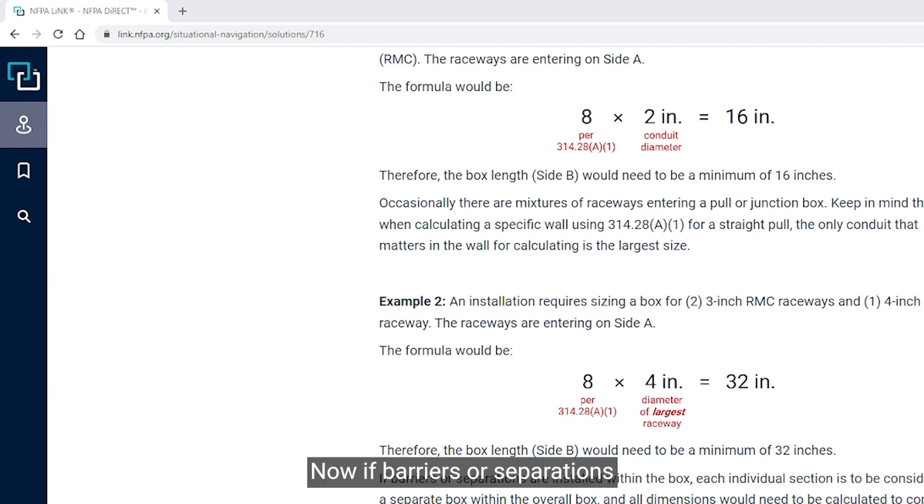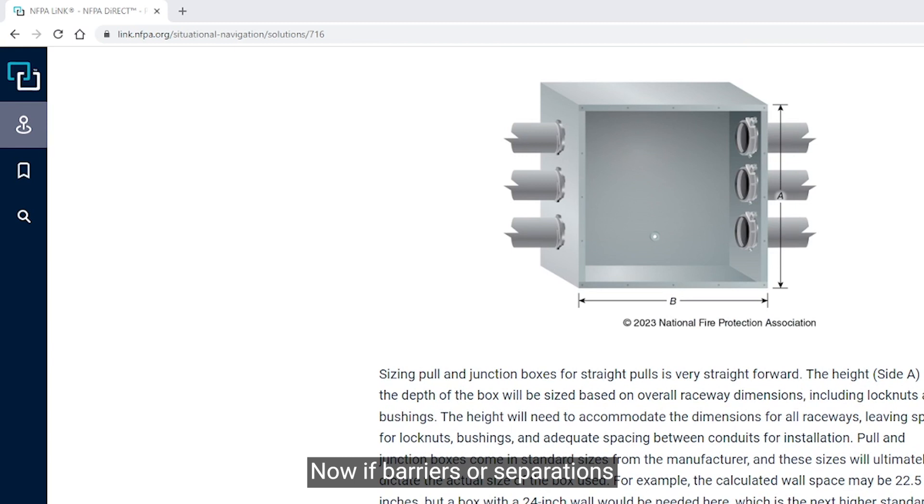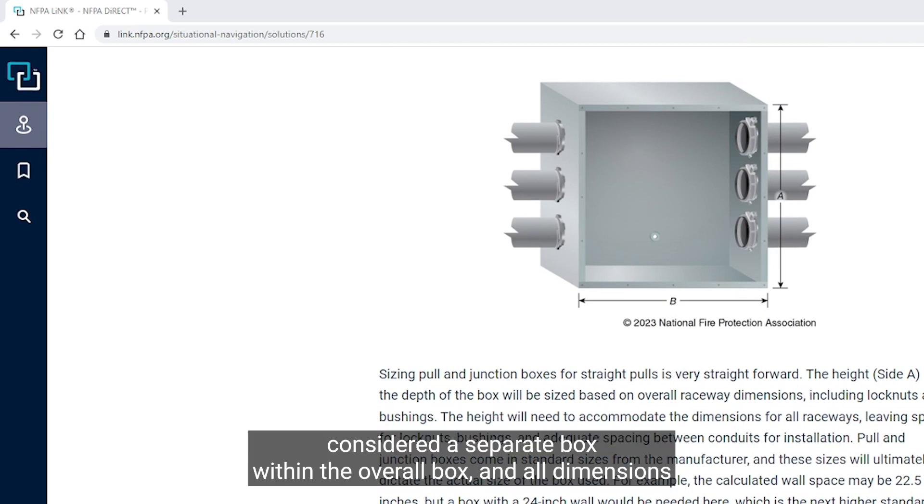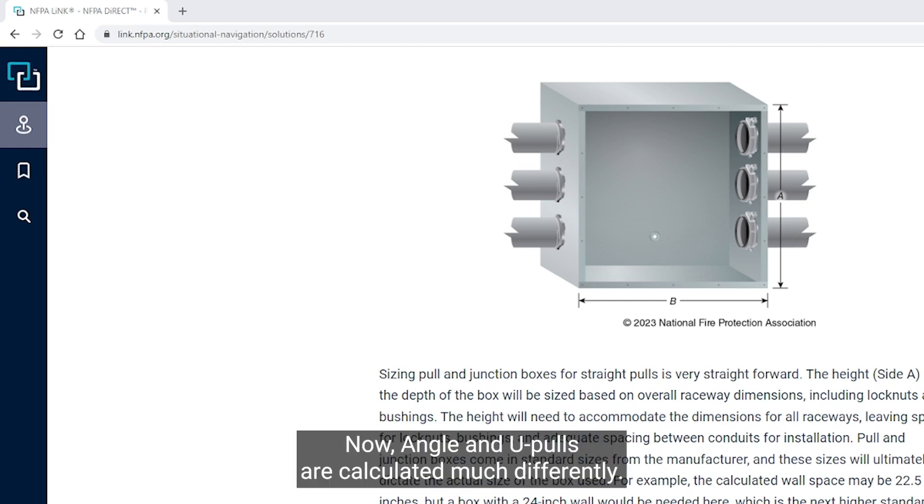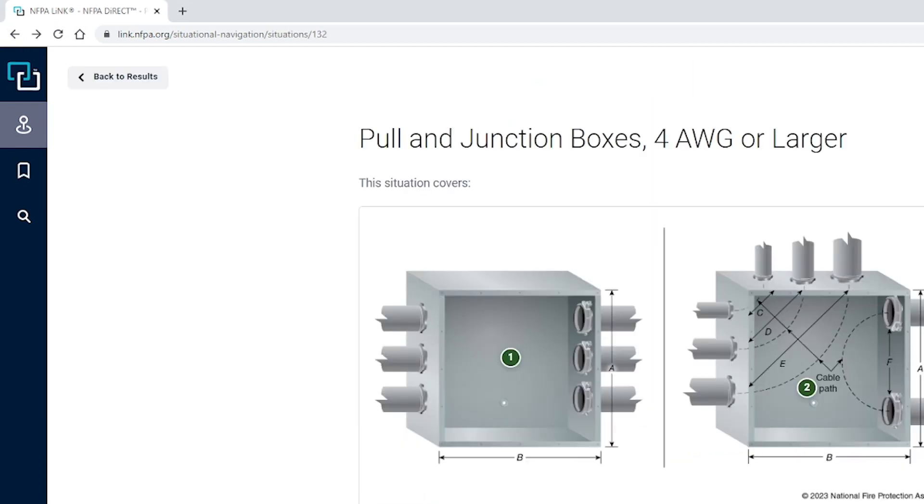Now, if barriers or separations are installed in any way, then those individual sections are to be considered a separate box within the overall box, and all dimensions would need to be calculated to comply with the NEC for each separate space. Angle and U pulls are calculated much differently. Let's go to angle and U, Read more.